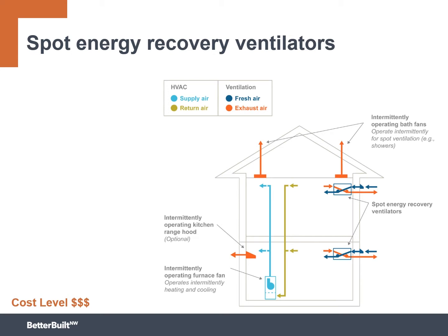So while it is tempting because they're not incredibly expensive individually and can be fairly easy to install, you may need multiples of them. Also, again, as I mentioned previously, these are not truly distributed, so they're not really able to move air into all the bedrooms in the main body because, as is indicated, they are a spot system. So for the Washington State Energy Code, where there's a ventilation adjustment required if you're not balanced and distributed, you would actually need even more air. So again, 2 or 3 or 4 of these devices may actually be required if you're choosing this methodology.